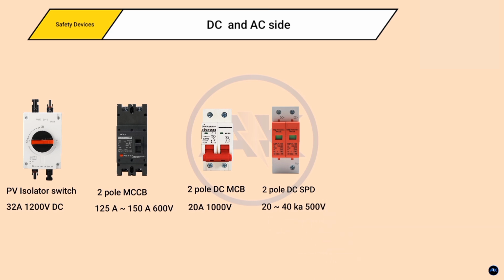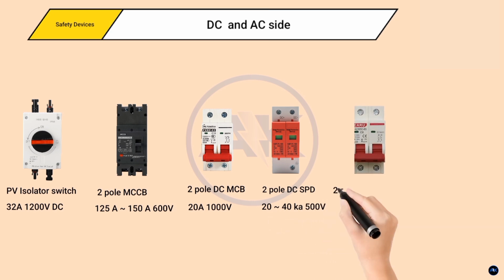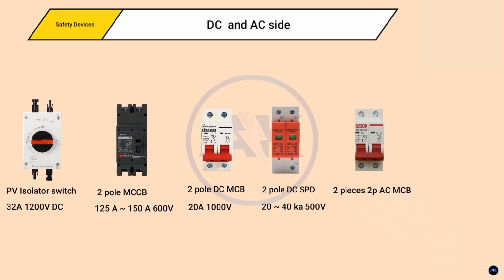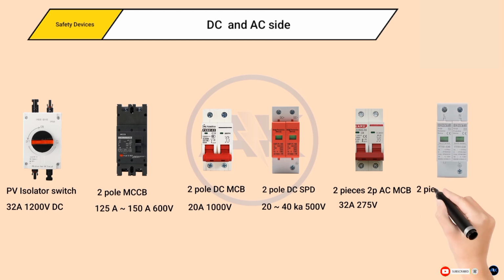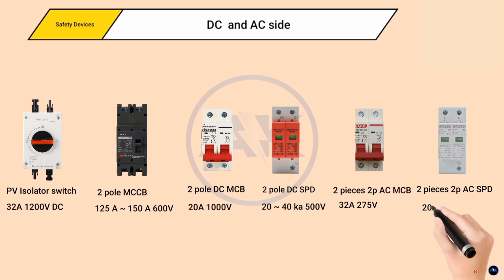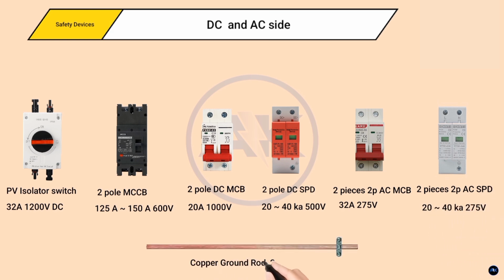And of course we're going to use AC MCBs, 2 pieces of this. We're going to use one for the hybrid inverter input and another for the AC output, rated 32 amps, 275 volts, or you can have a higher voltage rating. And 2 pieces of 2-pole AC SPD rated 20 to 40 kA, 275 volts. Last on the list is the copper ground rod. The length is 2.4 meters.